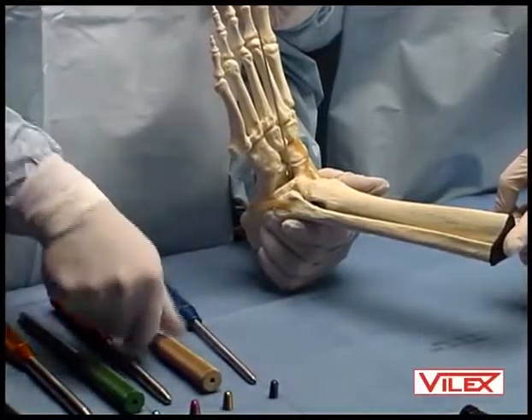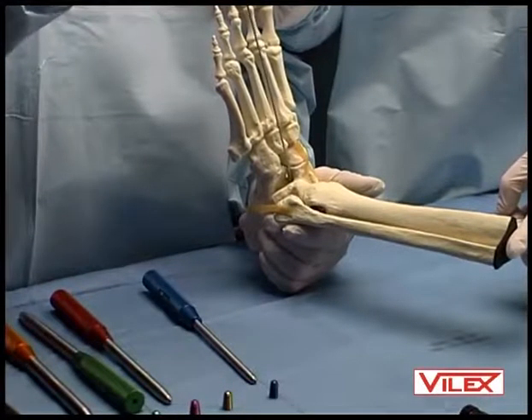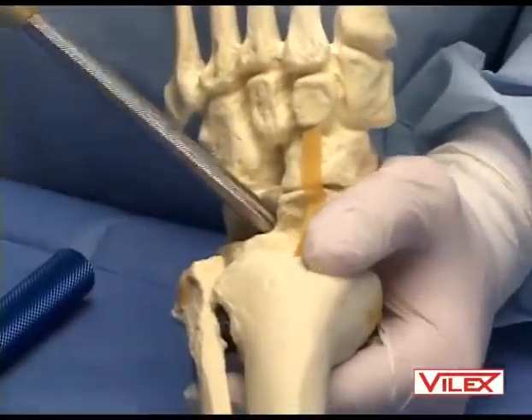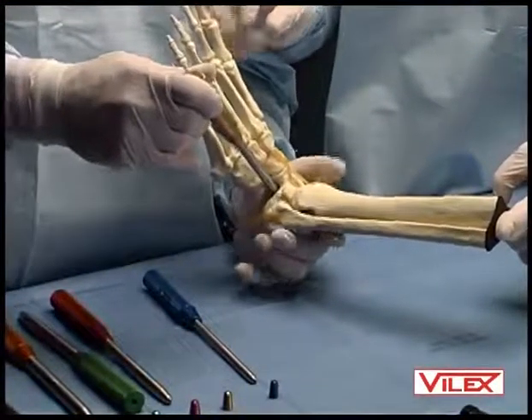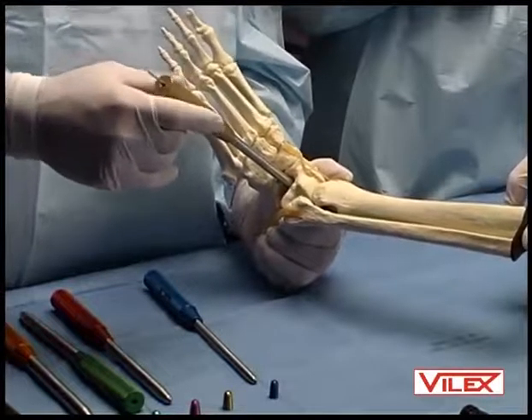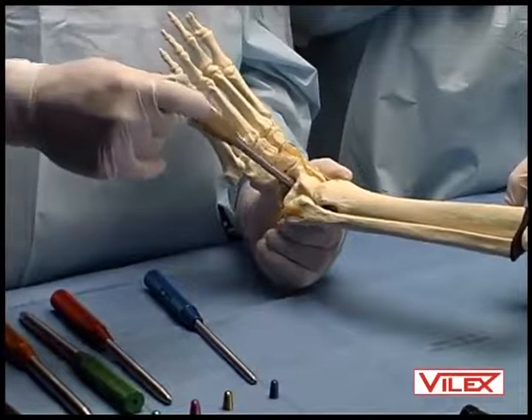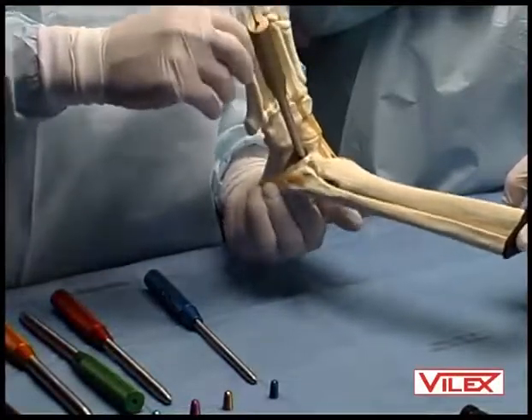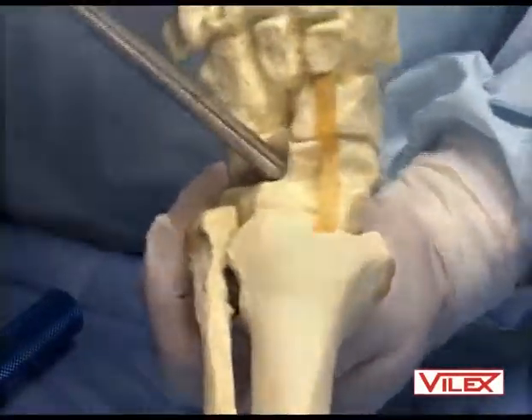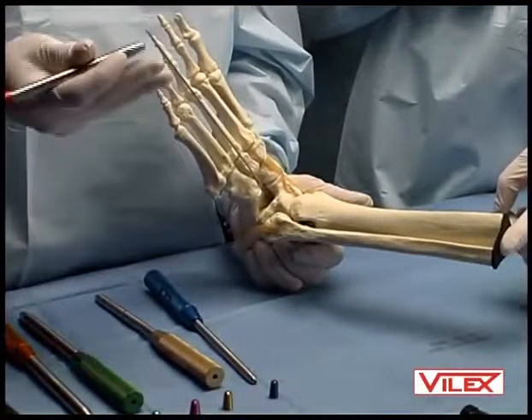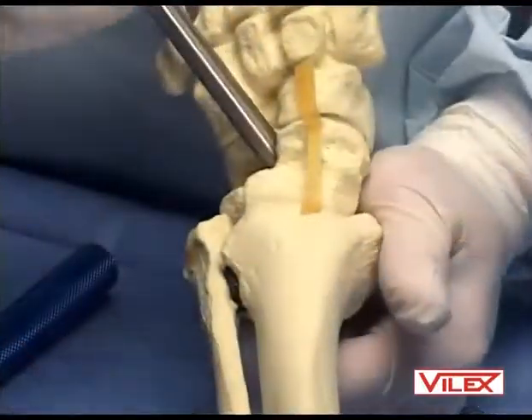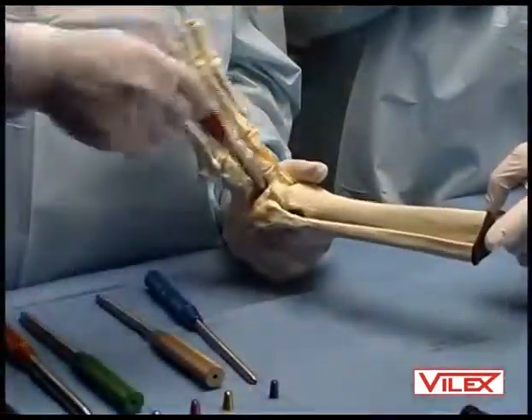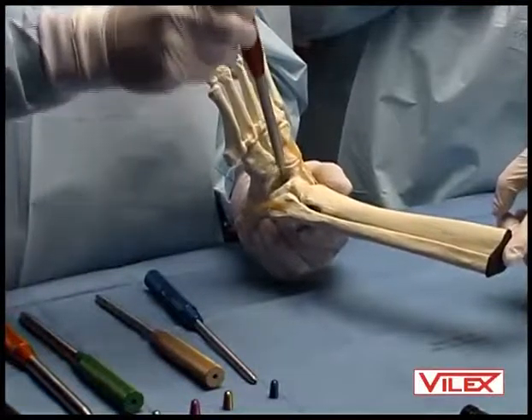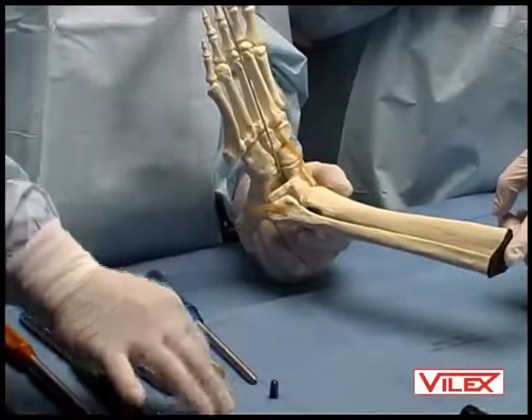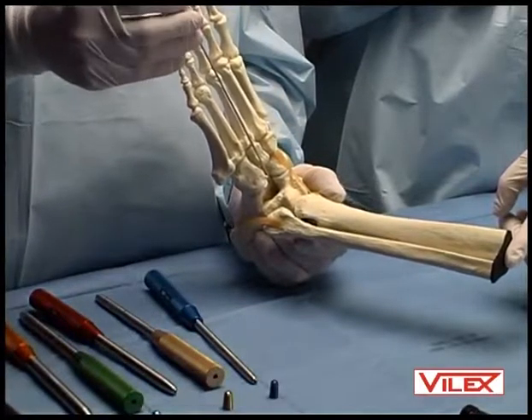And now I advance to the 9 millimeter, which is color-coded with the actual implant. Makes it for ease of use and understanding. I pass it in, start to feel it compress into the sinus canalis, and you can check with a C-arm to make sure that you're not advancing it too far to where the diameter of the probe is causing too much dilation. Again, feel for the mid-tarsal joint and feel the calcaneus. We'll advance to the next size, pass it on, and this being the size 10. Again, feel to make sure it's the right size, check with a C-arm, take it off, insert the actual implant. So in this case, we're going to go with a size 10.